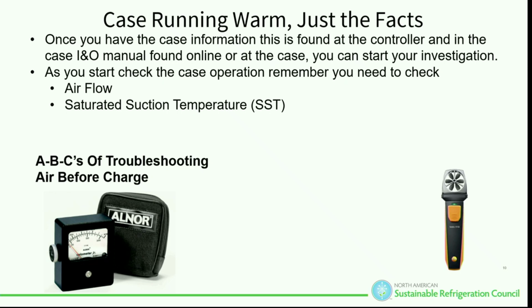That is what we're going to use in order to check the airflow to make sure it's actually correct. If you do not check that with that type of device or an anemometer, and you just call it good, you're probably going to have a problem later on down the line. Once again, sorry, saturated suction temperature: we want to make sure that's within tolerance of what the case spec is supposed to be, and that's why checking airflow is so important.